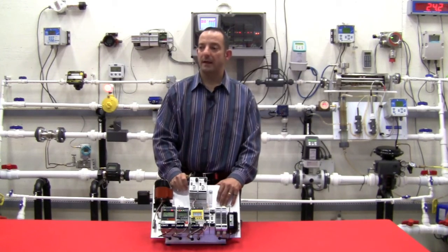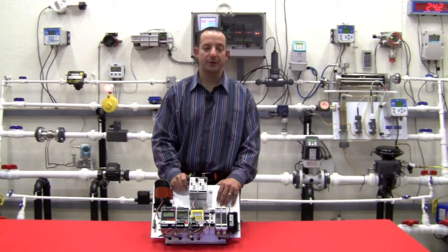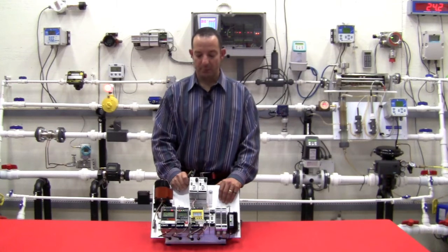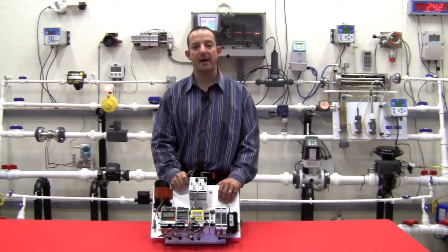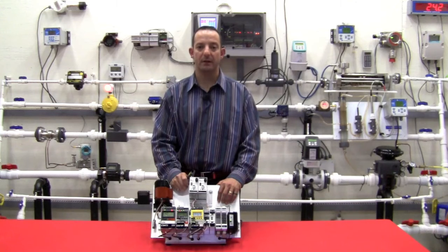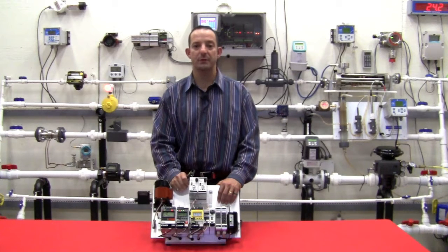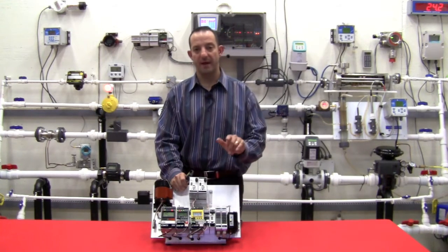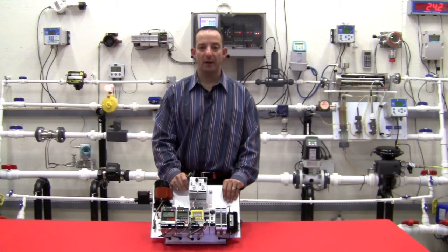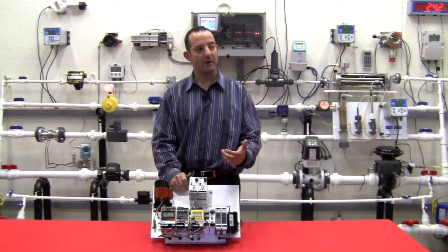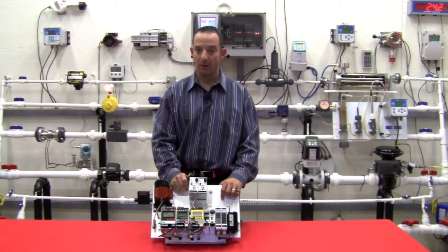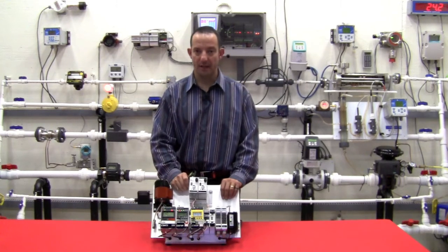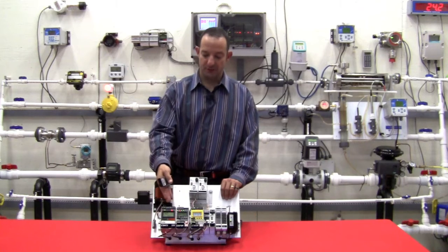Or any other HART transmitter used in a critical application is a good candidate for an HIM, because a lot of those smart transmitters have diagnostic fault information. For example, if a pressure transmitter's diaphragm ruptures, there's a HART digital fault bit that the transmitter will set, but you wouldn't know it unless you're hooked up to the loop with your HART handheld communicator. Or if you've got an HIM on that loop, that's essentially what you have.